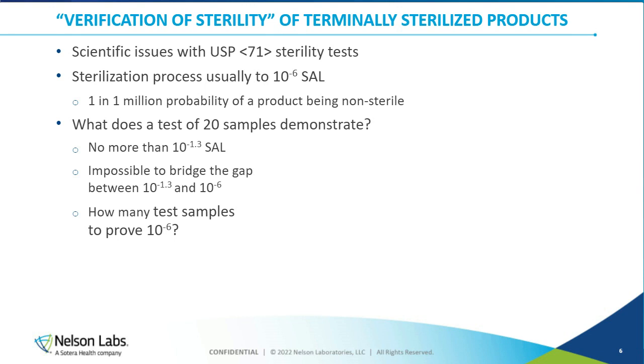Let's say you test 20 samples, so 20 samples demonstrates an SAL of 10 to the minus 1.3 as far as sample size goes. So how do you bridge that gap between 10 to the minus 1.3, what you've actually tested, and 10 to the minus 6, which is what you're trying to verify? So how many samples would you have to test to actually verify 10 to the minus 6? Of course, at least 1 million samples, if not 3 million, if you want to do some statistics there. Some people say 3 million would be necessary.